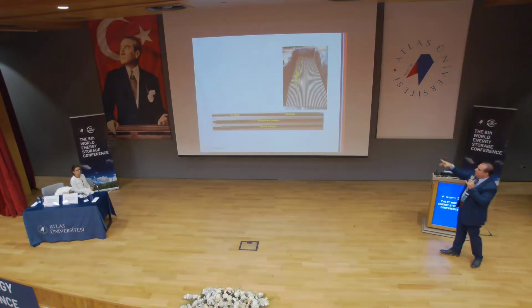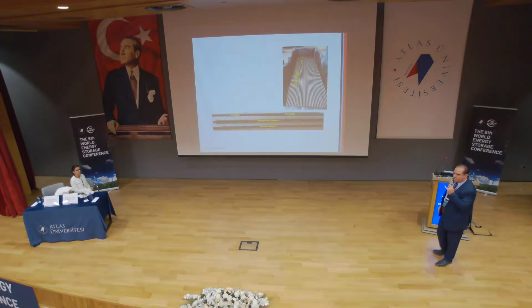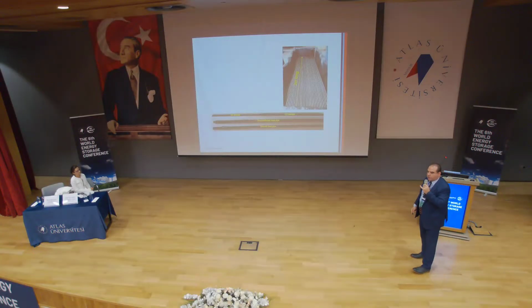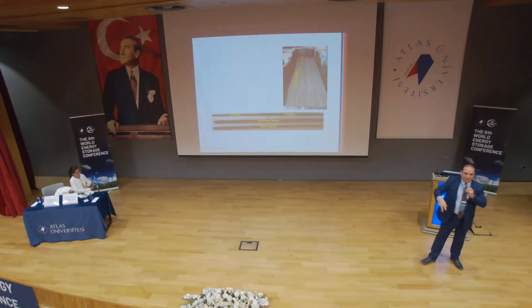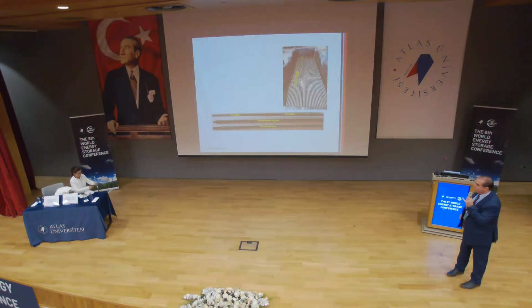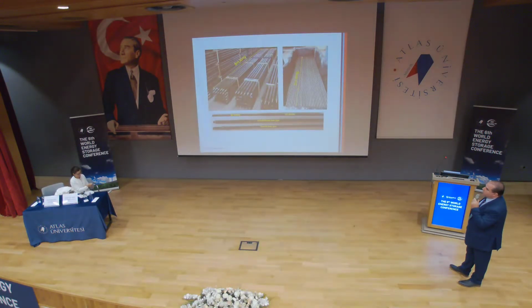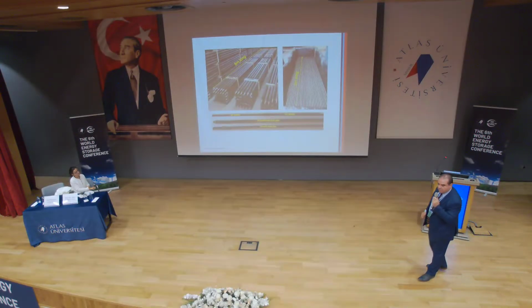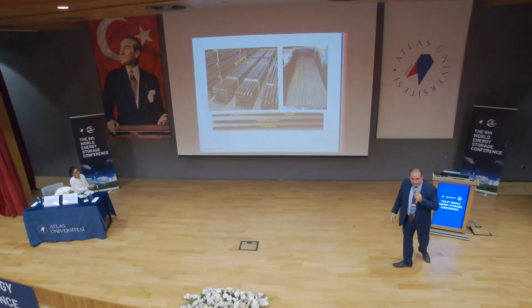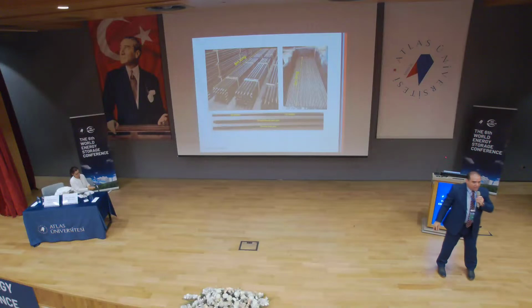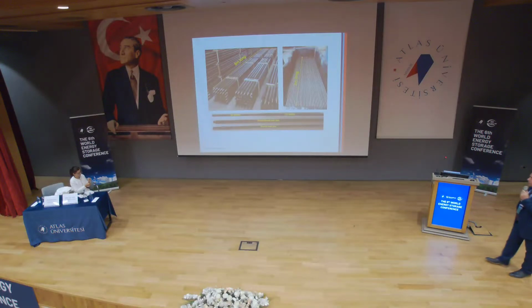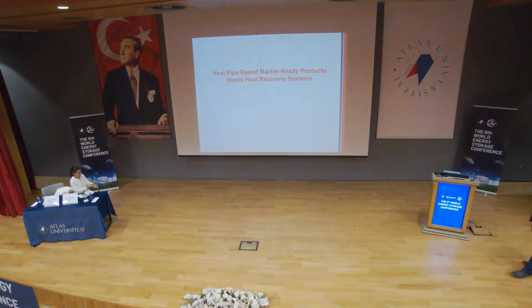Lots of things happening. This box actually went to India to be installed in a ceramic company. Everything was ready, the heat pipes arrived under supervision, were installed, and the system was commissioned in less than a week. We made heat pipes up to 20 meters in length. There's no limit regarding the dimensions; you just have to design it properly so it functions without hitting any of its limitations.